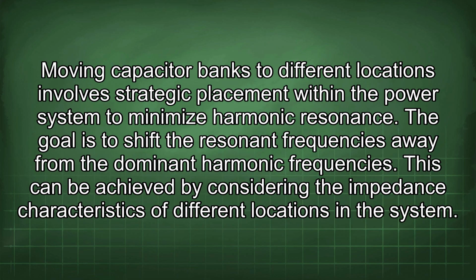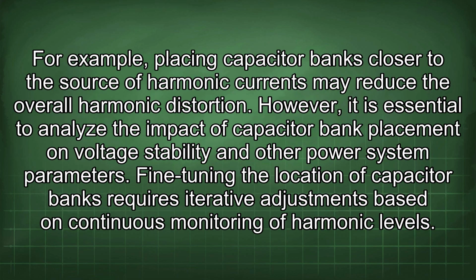Moving capacitor banks to different locations involves strategic placement within the power system to minimize harmonic resonance. The goal is to shift the resonant frequencies away from the dominant harmonic frequencies. This can be achieved by considering the impedance characteristics of different locations in the system. For example, placing capacitor banks closer to the source of harmonic currents may reduce the overall harmonic distortion. However, it is essential to analyze the impact of capacitor bank placement on voltage stability and other power system parameters.